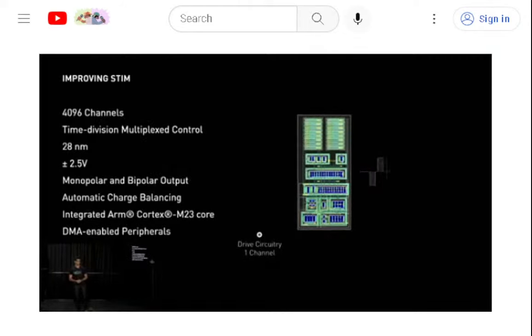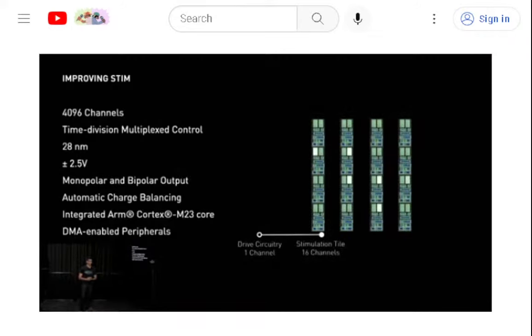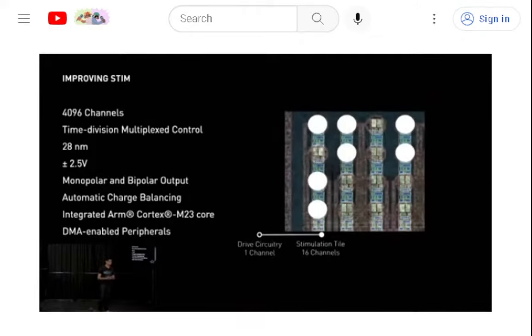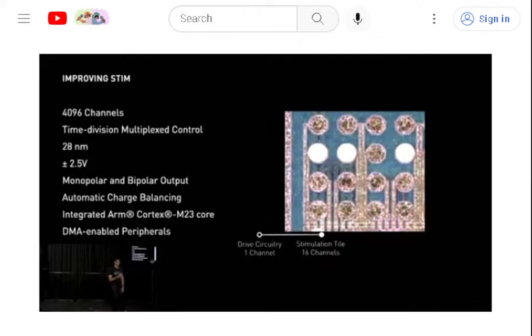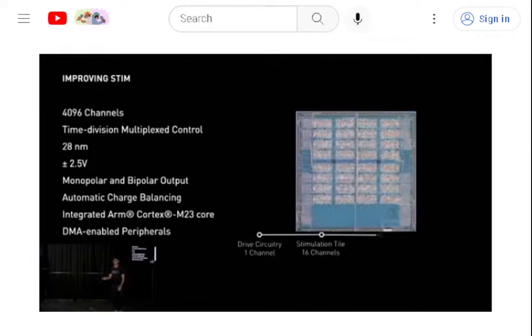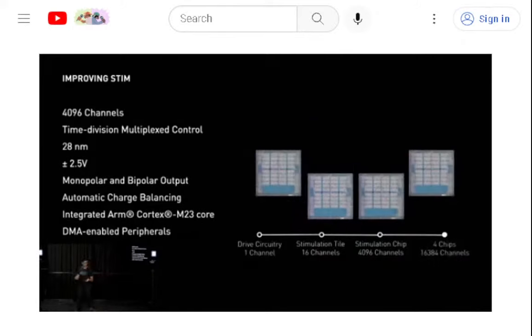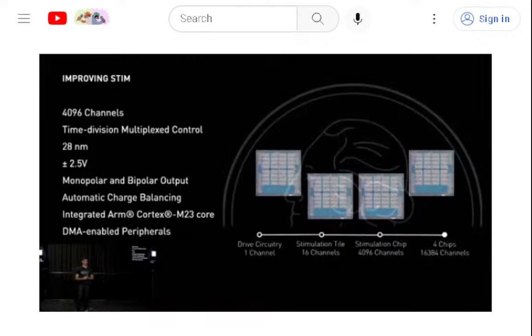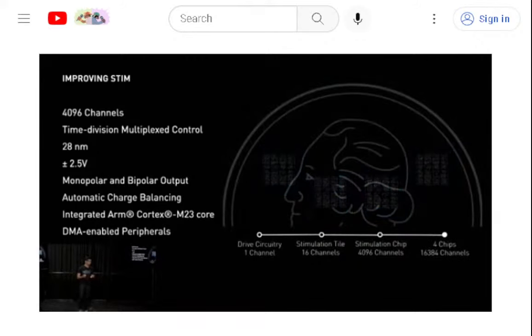We're also working on a next generation stimulation-focused chip with 4,096 channels still within the footprint of our current chips. In addition to increasing the channel count, we're also increasing the drive voltage so we can get better activation per channel. And to support this higher channel count, as well as a broad range of future applications that you'll soon hear about, we're adding an ARM core onto the chip. And finally, since these chips are the same size as our current chips, we can still put 4 of them together into a single implant for a total of 16,000 channels still within the size of a quarter.